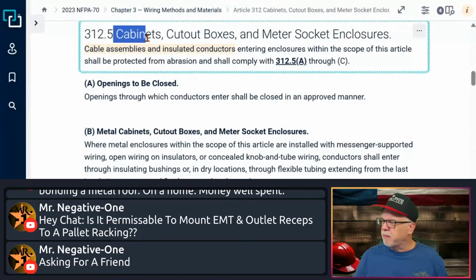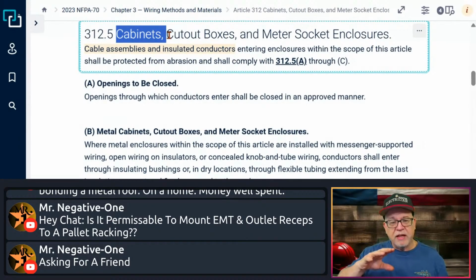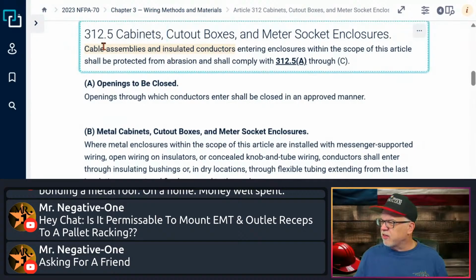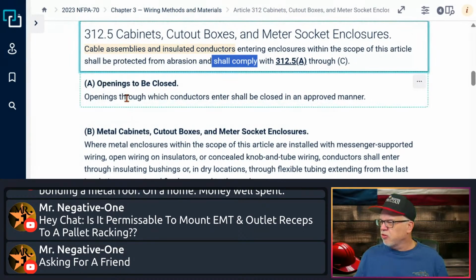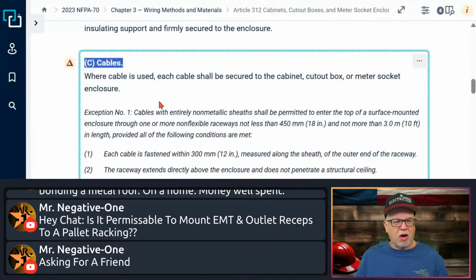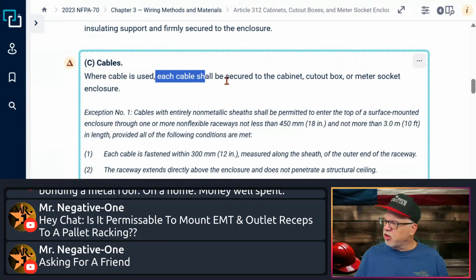So this is for cabinets, cutout boxes. Okay, a cabinet obviously is where the cables are coming into your cabinet. So it says cable assemblies and insulated conductors entering enclosures within the scope of this article shall be protected from abrasion and comply with 312.5 A through C. So it says it shall comply, mandatory requirement. Okay, so cables, C. So all you out there that are bringing all of those cables through the back of a TA, like Mr. Porter out there likes to see out there in Arizona, it says where cable is used, each cable shall be secured to the cabinet, cutout box, or meter socket enclosure.